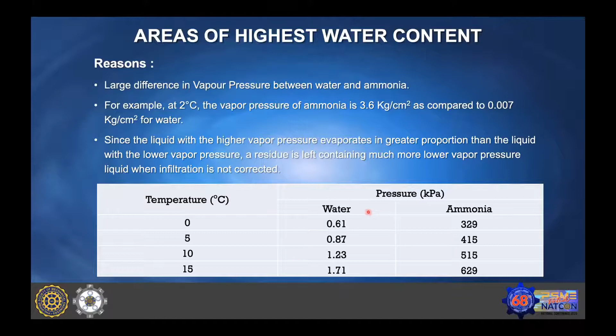So the question comes: how do I know there is water in my system? The simplest way of knowing is that you are not able to maintain the rated evaporating temperature at rated suction pressure. If your plant is not able to maintain it, that definitely indicates that there is water in your system.